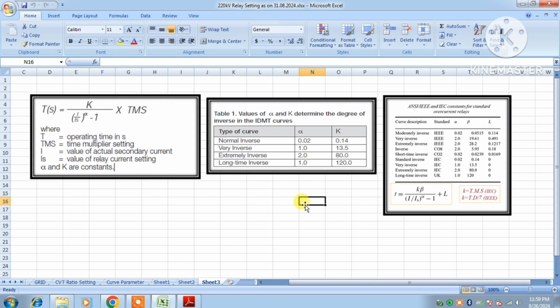Our application is designed based on the IEC curve. These IEC curves are normal inverse, very inverse, extremely inverse, or long time inverse. SI3 is standard inverse 3, which is equal to the normal inverse curve. So SI3 and NI are both the same. The application we are going to discuss is based on this IEC curve only.